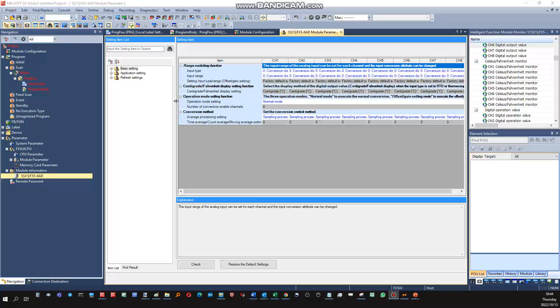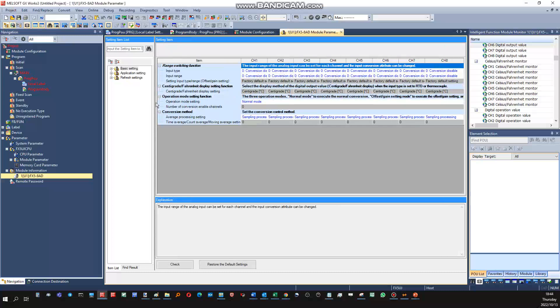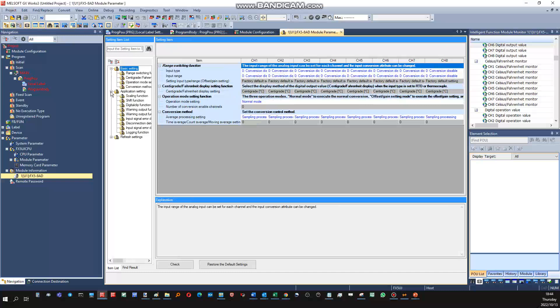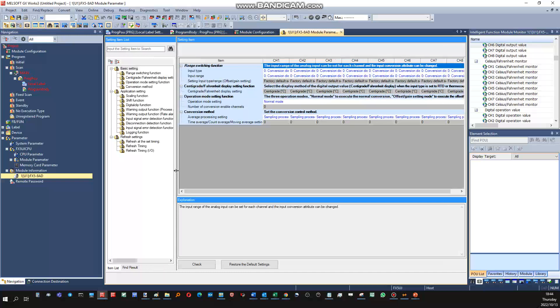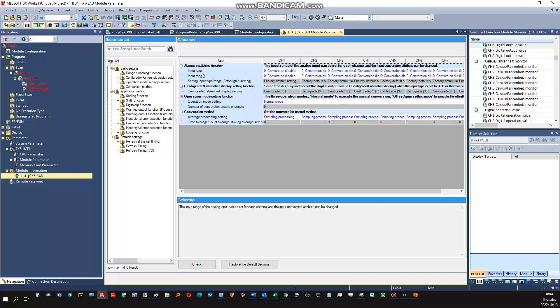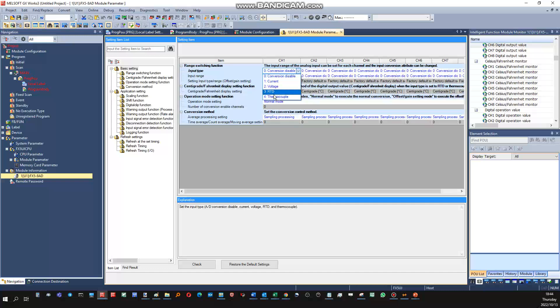Now that we have the room here, this will be the menu of the areas, functions and features to be configured. First things first, as mentioned, there are eight channels which can be enabled and configured here. Looking at channel one, input type is disabled, so we can select RTD, thermocouple, voltage, or current. For this test we will look at currents, so let me set them to current.